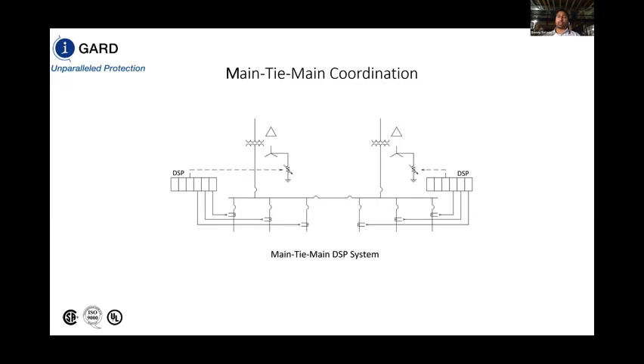And as a result, we have a system that is compatible with such a configuration. We place our DSP system on the left-hand side, monitoring the resistor on this transformer, and we have another DSP system on the right-hand side, monitoring the second resistor's transformer and its associated loads. When the tiebreaker closes here, we get a signal that the tiebreaker is closing, and the DSP system on this side will transfer over all of its readings to the DSP system on the other side to unify the priorities along the entire bus and continue monitoring these 3 feeders that are kicked out because this transformer was taken out for maintenance.